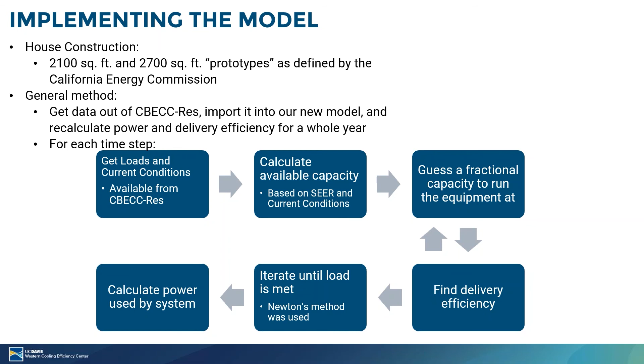Then we guess a fractional capacity to run the equipment at and calculate the delivery efficiency, or delivery effectiveness, from that. That's an iterative method - we guess and then use Newton's method until we figure out at what capacity to run this piece of equipment to meet the load. After we figure that out, we can figure out the power used by the system. We do this for every time step throughout a predefined year with defined weather, where temperatures, outdoor weather, cloud cover, and so on are available for each time step.